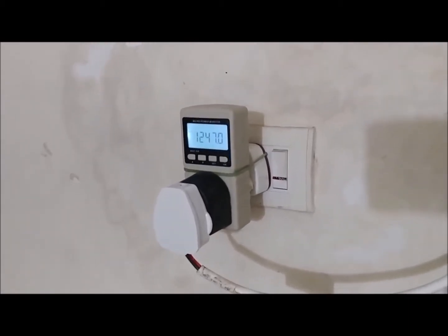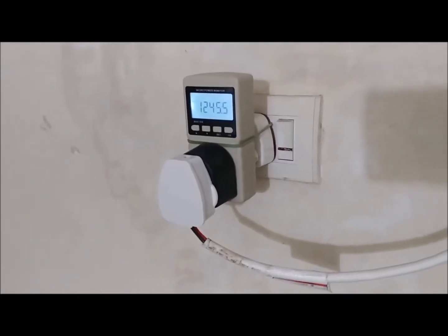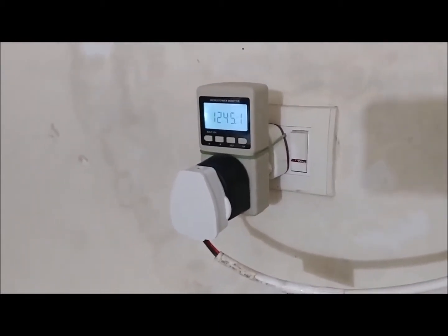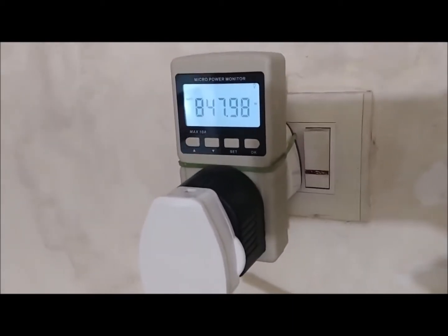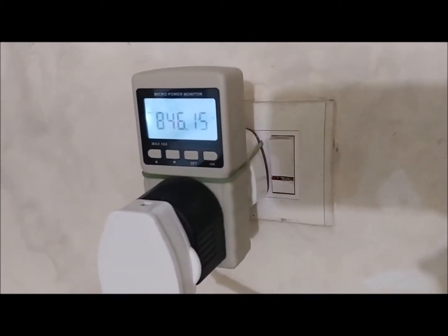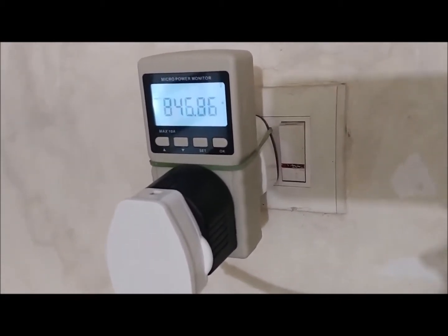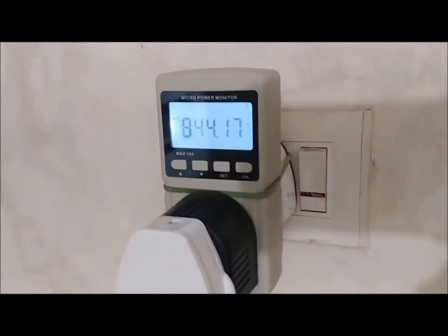Once the temperature falls down to 27 or maybe 28, in that range, then we'll see how much the power consumption is here. Now if you can see the power consumption, it is almost 10 minutes from the initial switching on time. Now it has fallen down to 800 watts. The rated power here is almost 1800 and it is consuming only 800. That is less than 50% of the power.